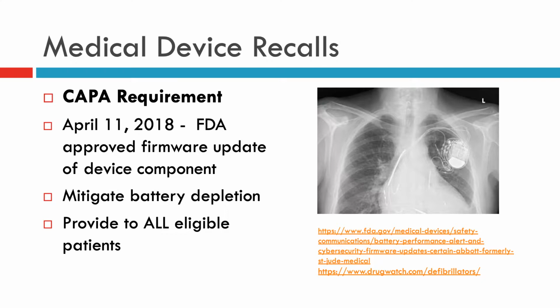On April 11, 2018, the FDA approved a firmware update that is now available, intended as a corrective action to reduce the risk of patient harm due to premature battery depletion and potential exploitation of cybersecurity vulnerabilities for certain Abbott ICDs and CRT-Ds.